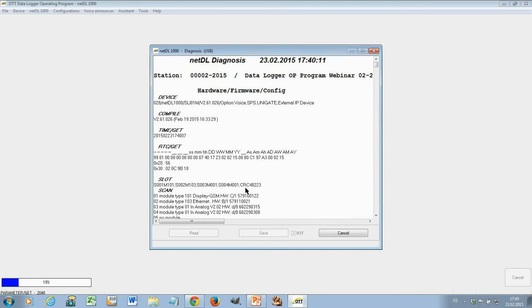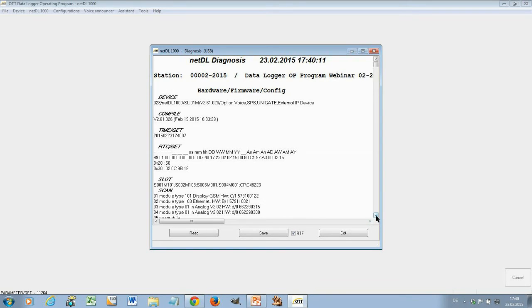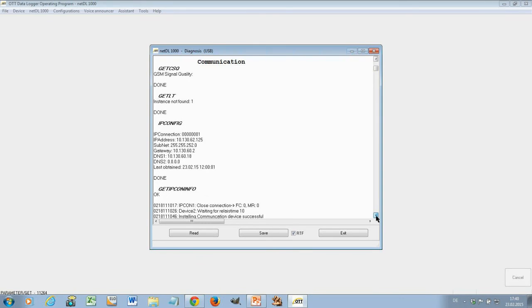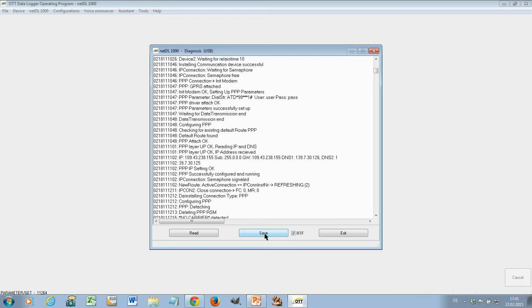It's still working on that. Now, it's done. What you see here is the date and when it's done, you see the station, the device, NetDL 1000, what is the firmware version, and what options are actually active. And here, you find all kind of information about the data logger and the communication. And in this information here, most problems can be identified very easily. You can save this to a file and for example, if you have a problem and you want to contact our HydroService, it's always very helpful to download this file and send this together with the actual configuration to HydroService. With these two files, the configuration and the diagnosis file, our HydroService should be very fast able to help you and to identify your problem.